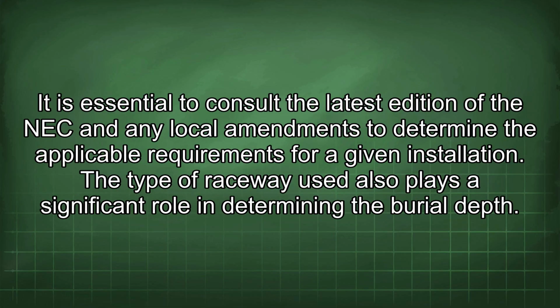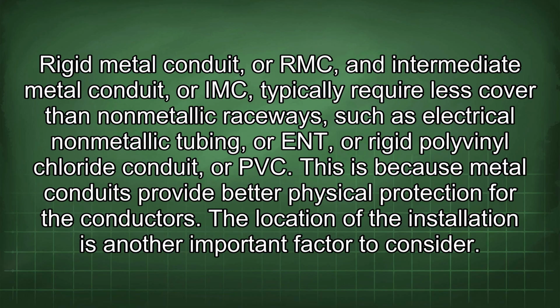It is essential to consult the latest edition of the NEC and any local amendments to determine the applicable requirements for a given installation. The type of raceway used also plays a significant role in determining the burial depth. Rigid metal conduit, or RMC, and intermediate metal conduit, or IMC, typically require less cover than non-metallic raceways, such as electrical non-metallic tubing, or ENT, or rigid polyvinyl chloride conduit, or PVC. This is because metal conduits provide better physical protection for the conductors.